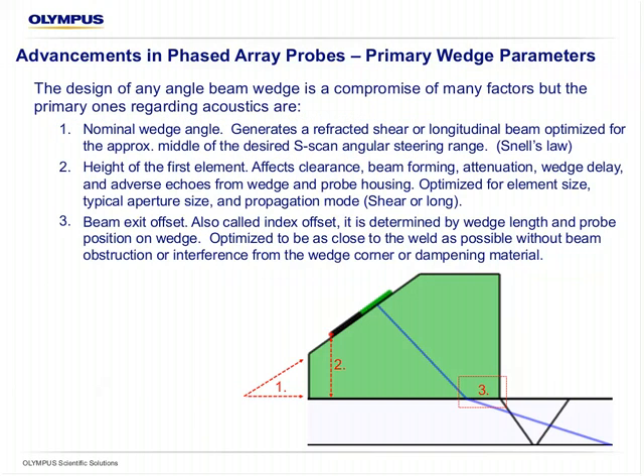So on any wedge design, there are many considerations, but the primary three are, first, the nominal wedge angle that generates either a refracted or longitudinal beam, optimized for the middle of the desired S-scan angular range. For Olympus, that's normally N55S or N60L. That means a nominal shear wave 55 in carbon steel. Second, the height of the first element. This is a compromise between clearance and beam formation for different apertures. It has a very important effect on longitudinal beam pulse echo wedges that we'll see in a couple slides.